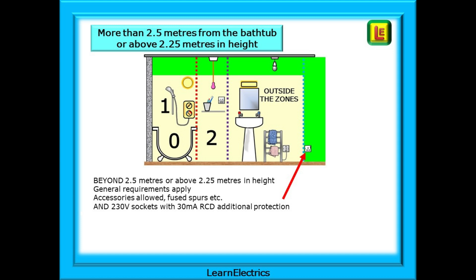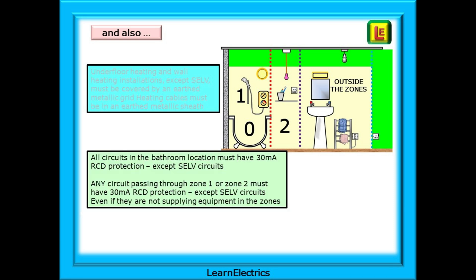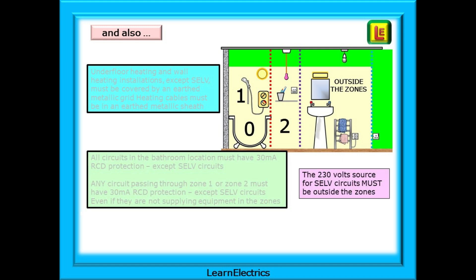Underfloor heating and wall heating installations, except SELV installations, must be covered by an earthed metallic grid, and the actual heating cables themselves must be in an earthed metallic sheath. This is the bathroom where people take their clothes off and stand on a wet floor — the regulations are there to make them safe. All circuits in a bathroom location must have 30 milliamp RCD protection, except SELV circuits. Any circuit passing through zone 1 or zone 2 must have 30 milliamp RCD protection, even if those cables and circuits are not supplying equipment in the zones.